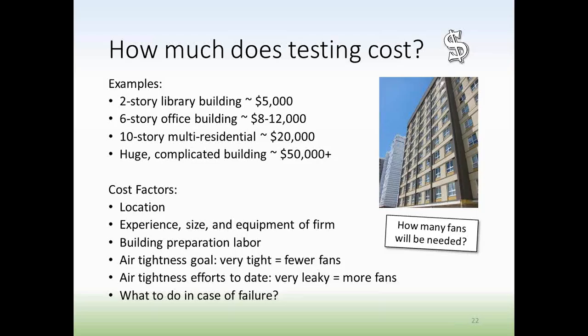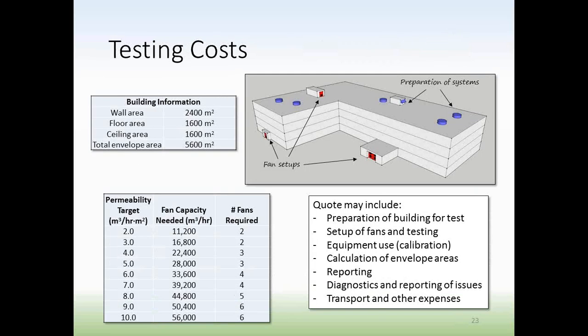Also think about what happens if you shoot for the air tightness and you miss it. So consider what you do in case of a failure. Just for example, with varying permeability targets, tighter buildings need fewer fans to accomplish the same depressurization. On the left here we have 10 cubic meters per hour per square meter, which would need 56,000 cubic meters per hour of fan capacity to meet that air tightness threshold. That's about 6 fans worth of fan power.